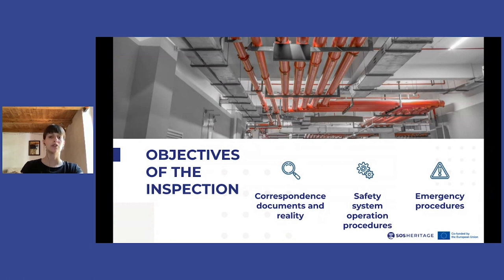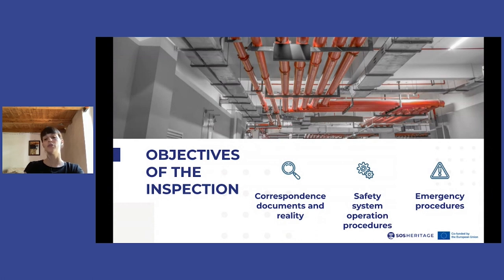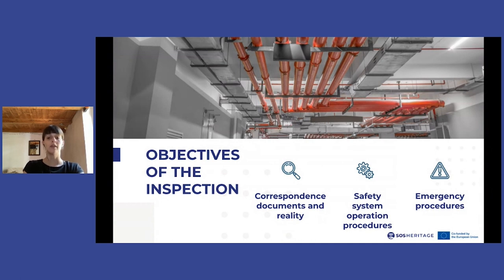It is also important to verify the emergency procedures in case of emergency. Some issues that can be investigated include the communication and intervention time of the fire brigade and rescue service team in the event of a fire, the alarm procedures in the event of an intrusion, the procedures for switching on the anti-intrusion system at the end of the shift, or the existence of a night patrol service, and so on.